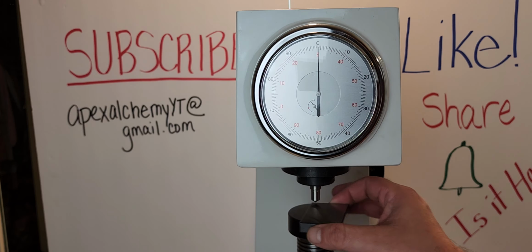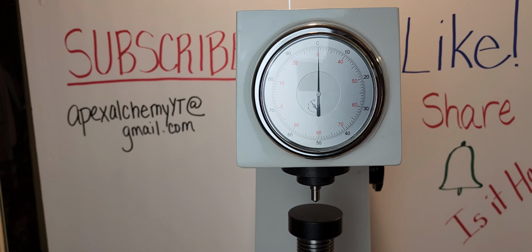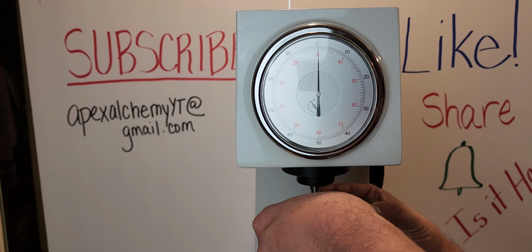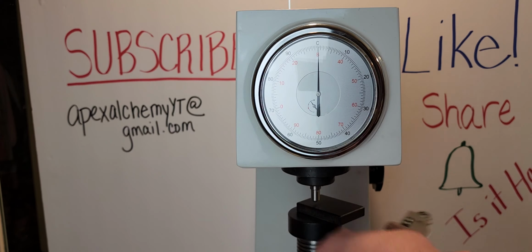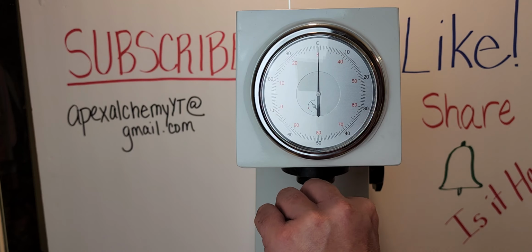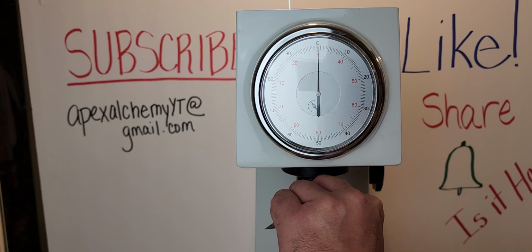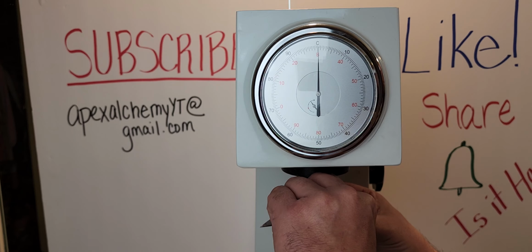We're good. It's off just a little bit, but I'm gonna call that. So okay, what I mean by it's off a little bit, the calibration's not off. It's reading 63 when it has applied pressure, but what is off is my little 0. Once that gets off a few points up there, I like to go ahead and redo everything. We've already poked it on this side. Frank, we're going to poke it on the other side just to get a measurement. We're going to go a little bit closer to the pivot track.